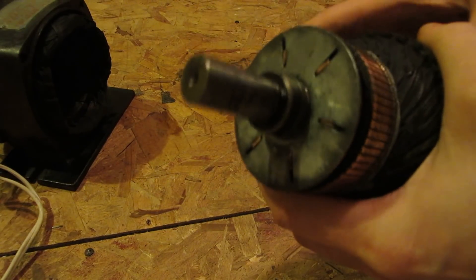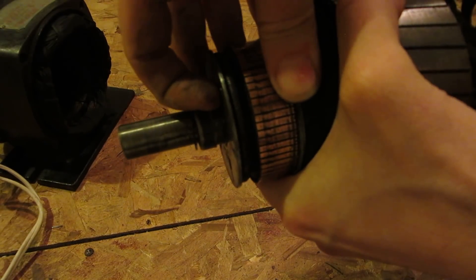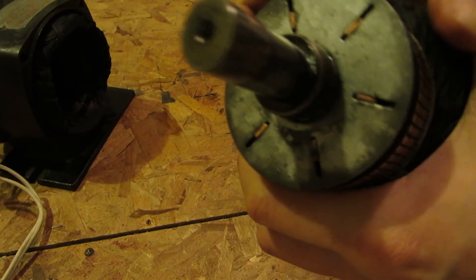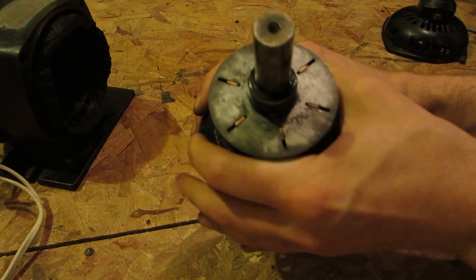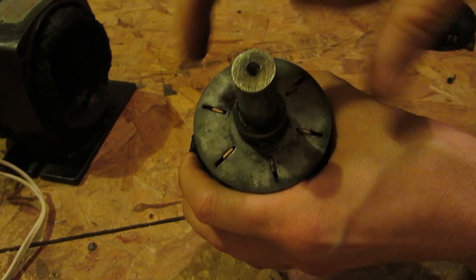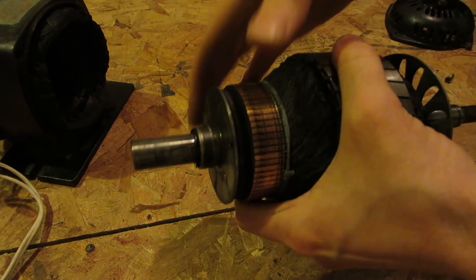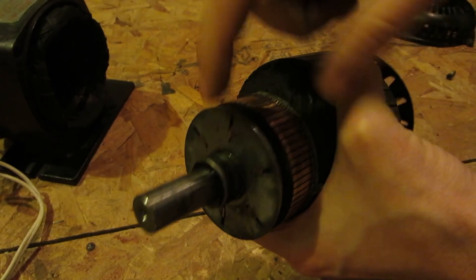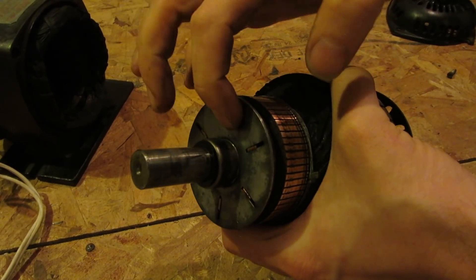When it reaches speed, these notches here — I can actually push on it — it raises your spring up. What these notches actually are is your electrical connections. So when they're in the down position, this here is actually engaged with the brushes. When these pull up, your brushes don't move away but they electrically disengage from this.